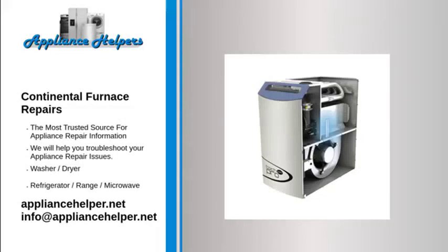If not, ensure that you have gas supplied to the furnace. You can do this by checking to make sure all of the manual isolation valves are on. If you have gas, the problem could be the gas valve or furnace control board. If the burners come on but do not stay on for more than about 3 seconds, the flame sensor could be dirty or the furnace control board could be bad.